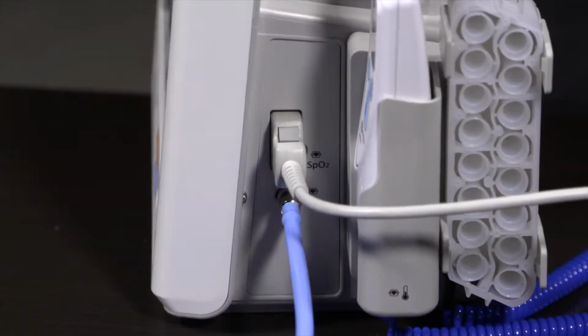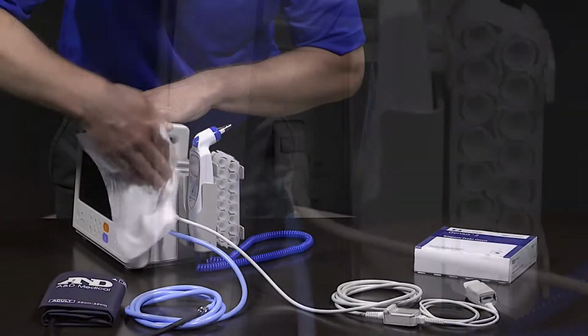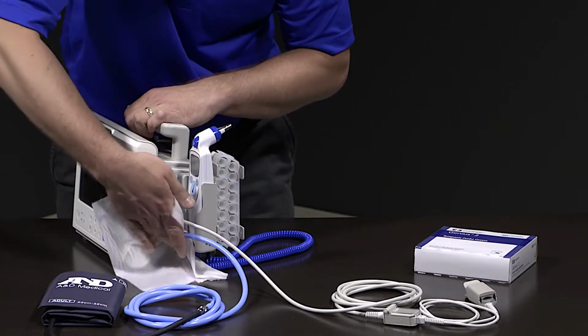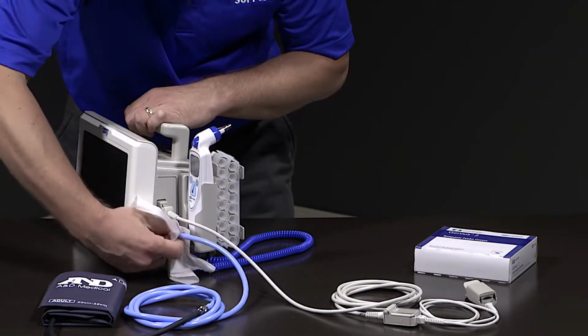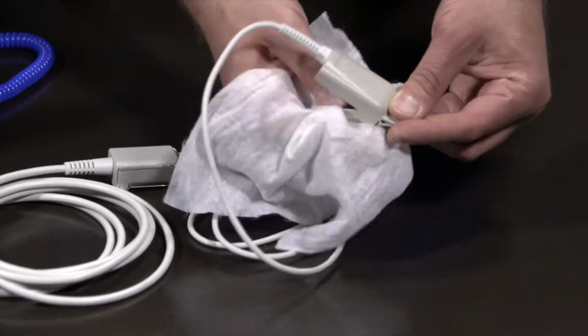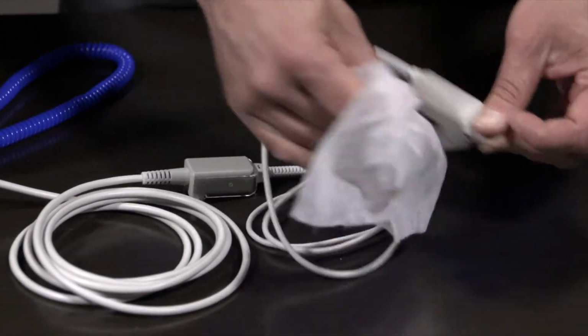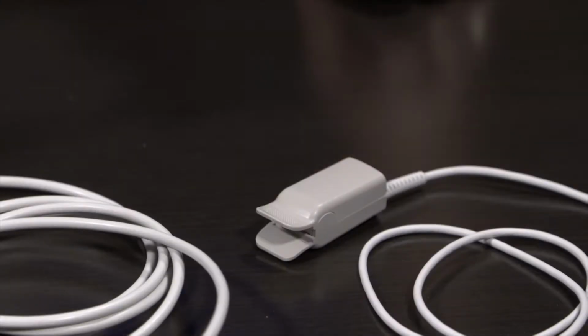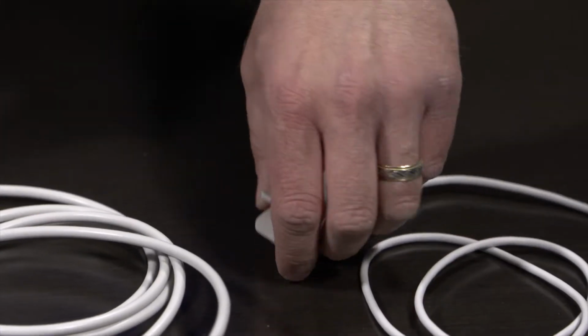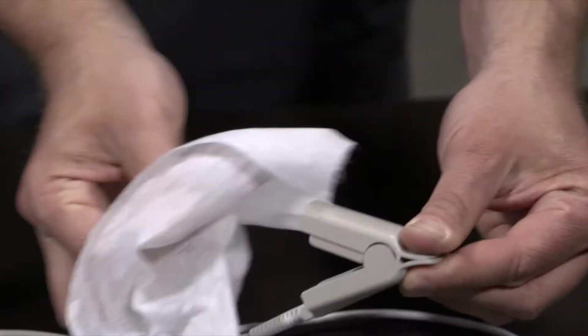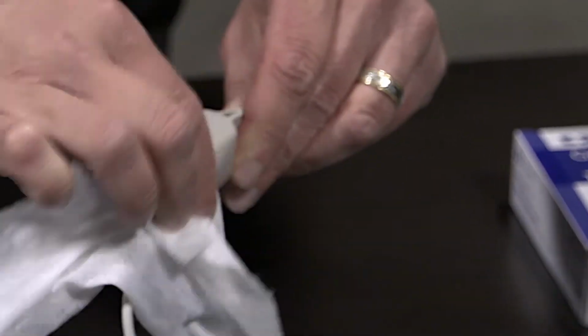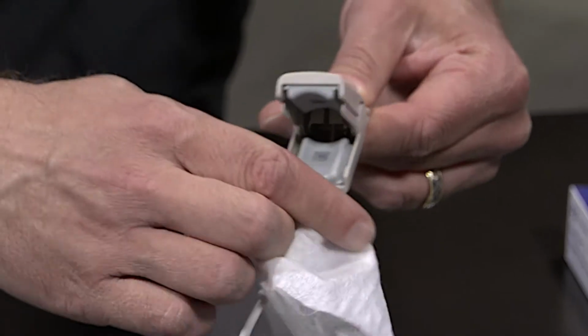Never allow any liquids to enter the monitor connector. If liquid does contact the connector, clean and dry thoroughly before reuse. Bleach solution can be used to clean the monitor and pulse oximeter fingertip sensor. For the sensor, let the bleach sit as long as needed to kill germs, but be sure to wipe away any residue. Letting residue sit too long on the sensor will deteriorate the device and affect performance.